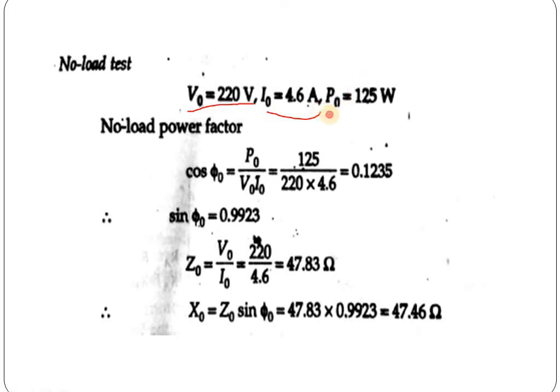Putting all those values in the power equation — we know P equals V·I·cos φ — where V and I values are known from the voltmeter and ammeter readings, we can calculate the power factor at no-load condition. That is, cos φ0 equals P divided by V0 times I0, which becomes 125 divided by 220 times 4.6. The power factor is 0.12.